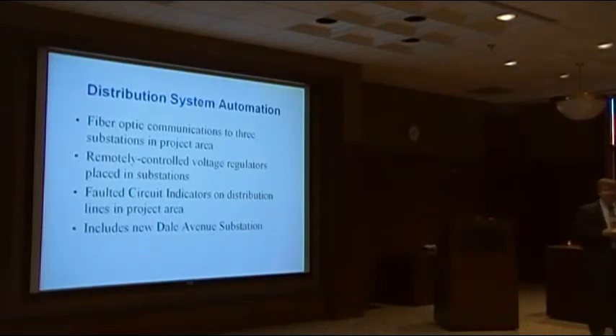One key to that, we'll use that communication system in all three of those substations, where we'll be installing voltage regulators, which will allow our system operations folks to monitor the voltage and look for the ideal state. If it's too high, they can lower it; if too low, they can raise it. All that will allow us to have a more efficient flow of electricity throughout that area and ultimately save system losses and save costs—we wouldn't be buying as much power from TVA as we otherwise would have. So again, a measure of efficiency there.